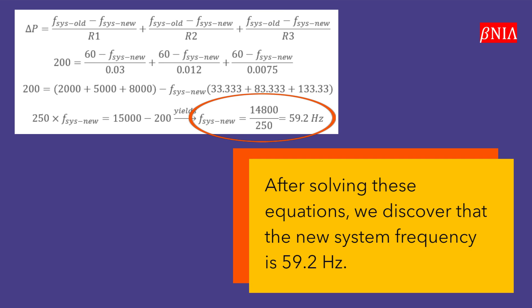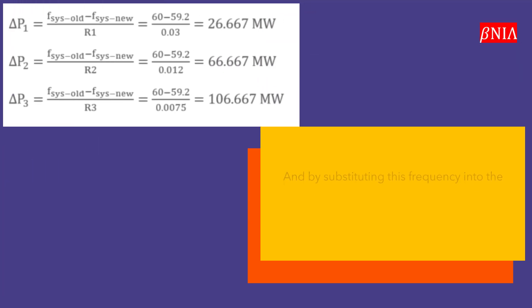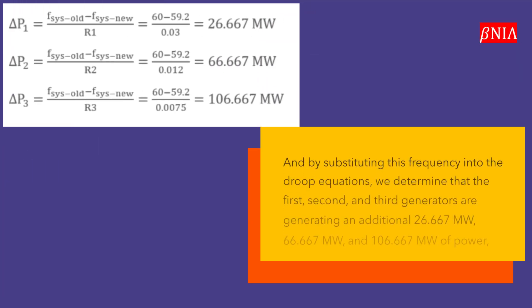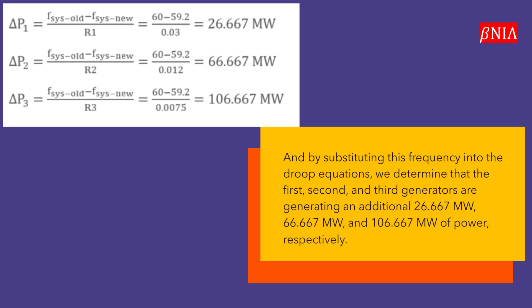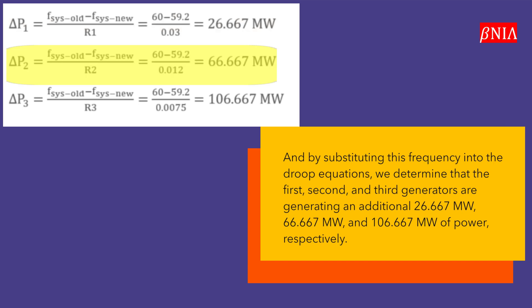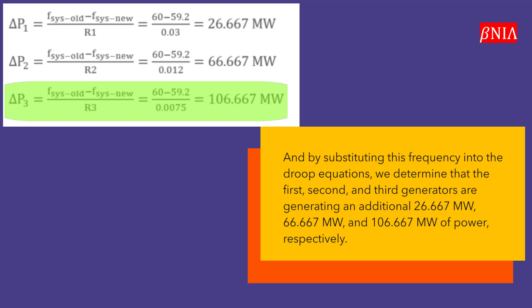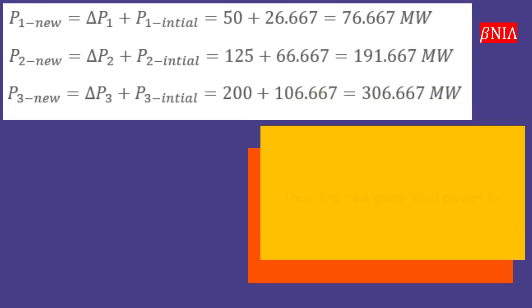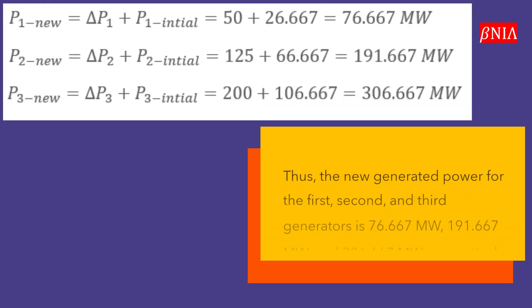By substituting this frequency into the droop equations, we determine that the first, second, and third generators are generating an additional 26.667 megawatts, 66.667 megawatts, and 106.667 megawatts of power respectively.